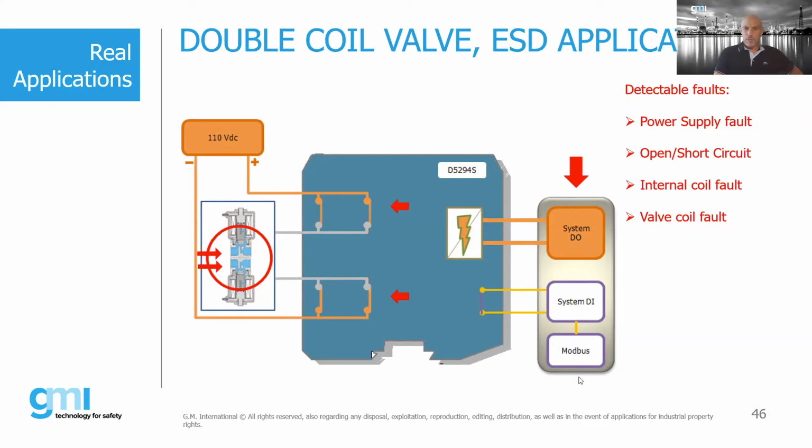Okay, we have another one. How is the Modbus interface for a multiple relay to a DCS to be done? Is it through some intermediate multiplexer? No, it's not necessary, because our relay can be directly connected to the PLC system if the PLC system has a master. Our relay works as a Modbus slave, and inside we can program a different address for each relay: 1, 2, 3, 4 up to 256 addresses on the same line. Okay, we can go through.